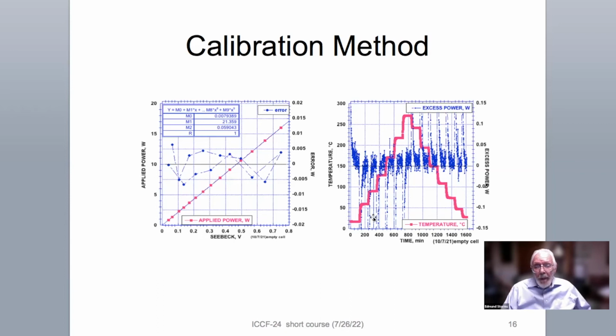The temperature in the calorimeter is caused to increase in steps. And this is the temperature of the inside of the cell that the sample would see. The temperature is maintained long enough for the calorimeter to come to constant temperature, which in my case is 100 minutes. But once that delay has been achieved and the constant temperature has been achieved within the calorimeter, the values now match zero, as they should.